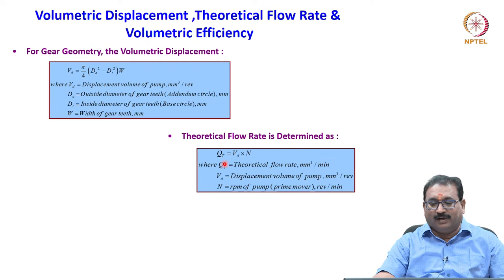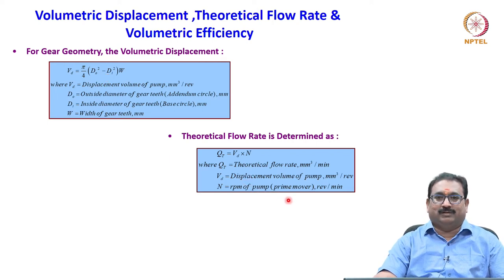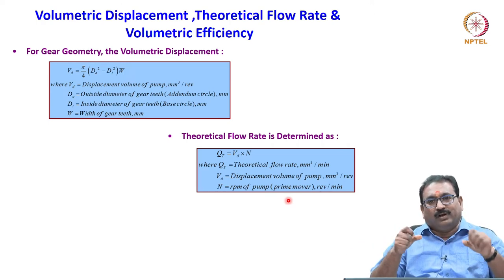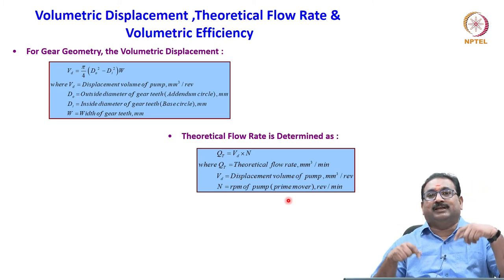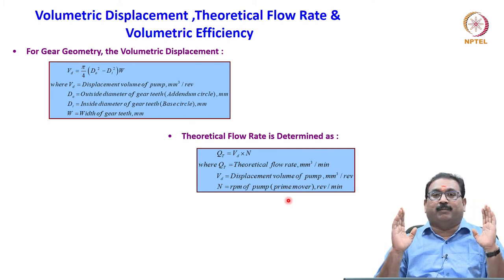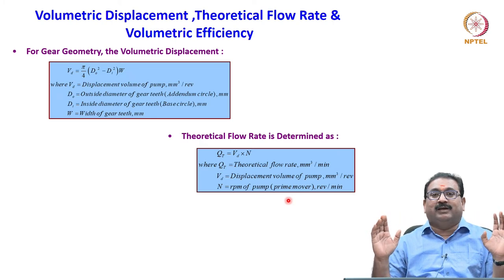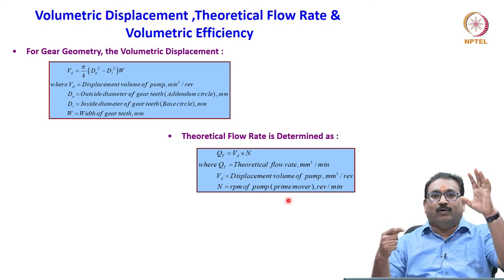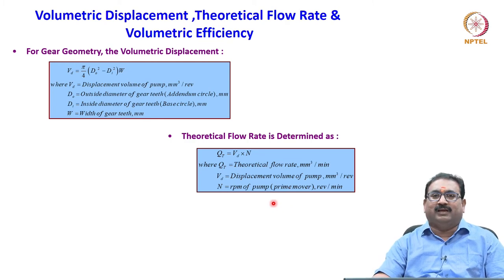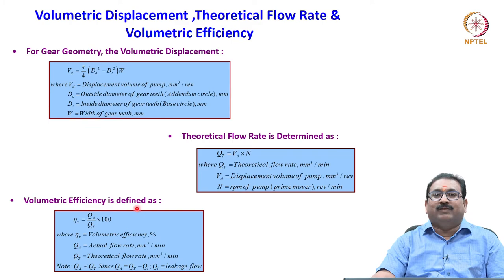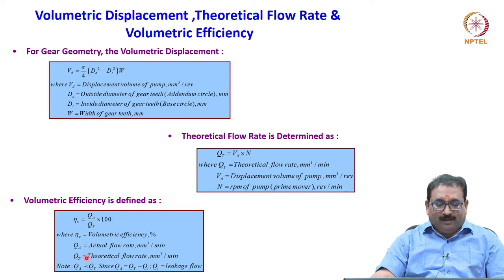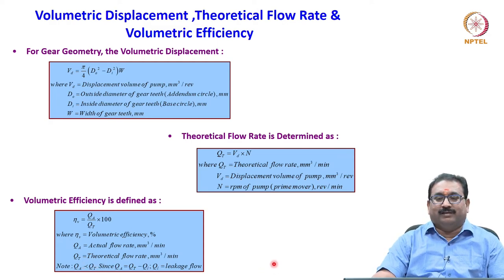Theoretical flow rate is calculated as Qt = Vd × N, where Vd is the displacement volume and N is the RPM of the motor. For one revolution, a fixed quantity is displaced — flow rate increases or decreases by rotating the shaft, but one revolution displacement remains the same. That is why gear pumps are always positive displacement pumps — no variability is available. Volumetric efficiency is defined as QA by QT × 100%. QA is always less than theoretical flow due to leakage from the gap provided in the mating elements.